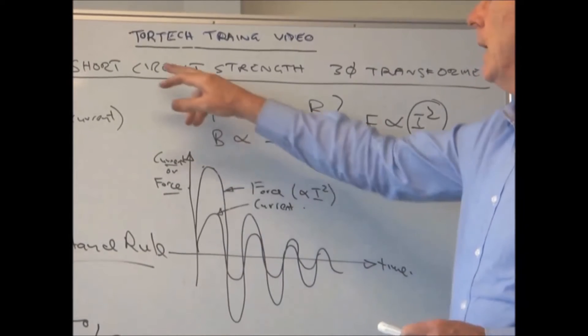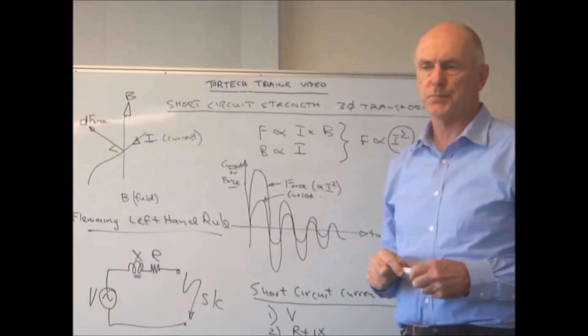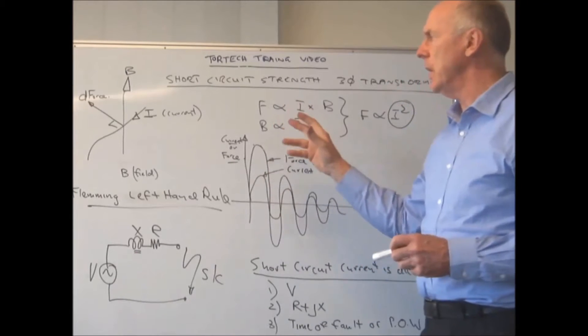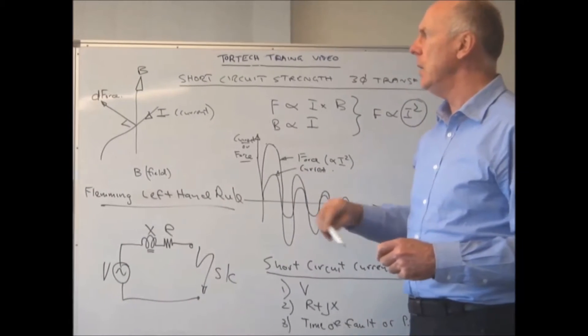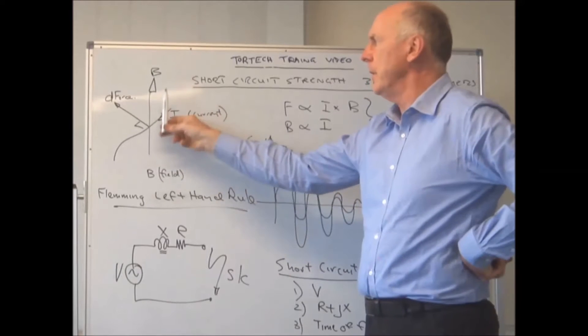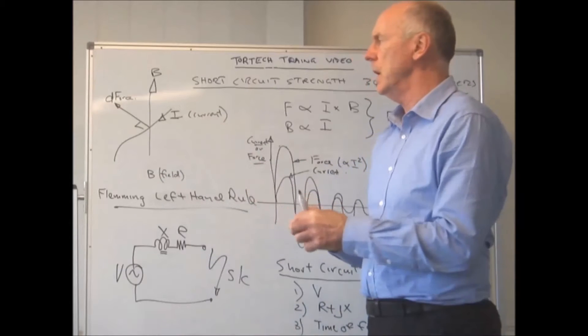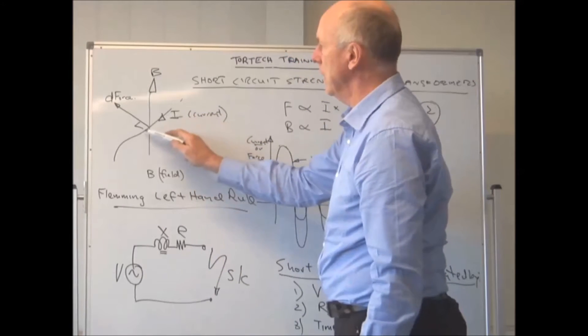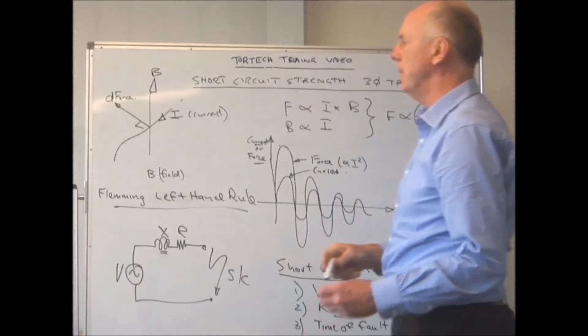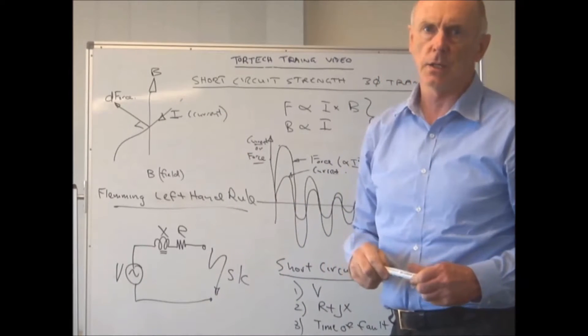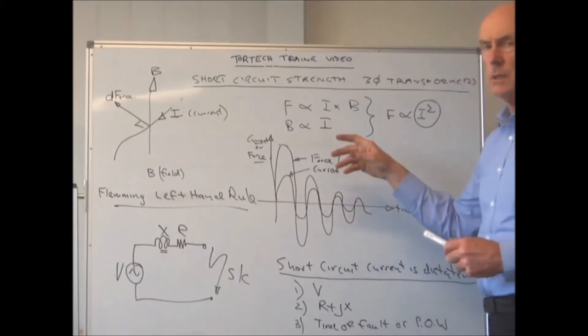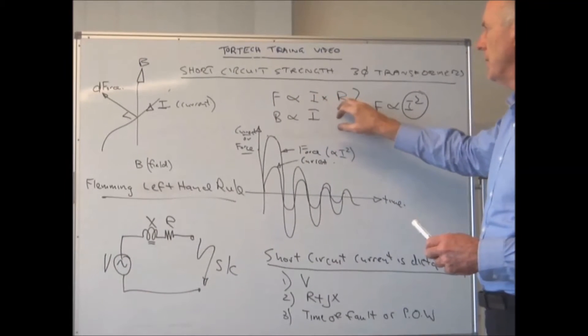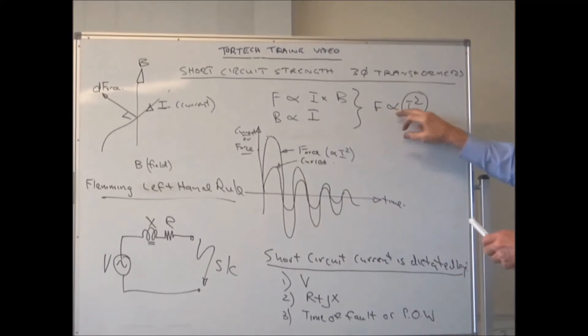Today we're going to talk about short circuit strength of three-phase transformers. The work is based around Fleming's left-hand rule. You can see the magnetic field, the current flowing, and the resulting force — the current is perpendicular to the field, perpendicular to the direction of the force. The force is proportional to the current times the field, and since the field is proportional to the current, the force is proportional to the current squared.